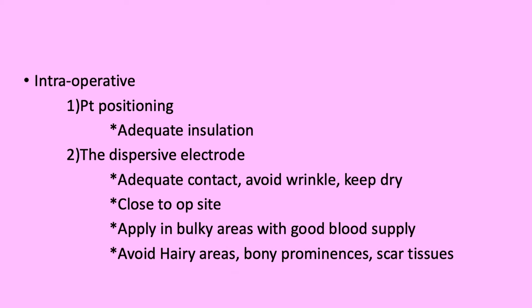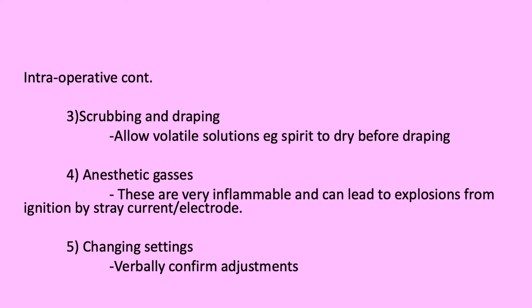The pad should be placed close to the operating site, because the further away it is, the longer the circuit, requiring more voltage to operate, which could result in burns to the patient. We should endeavor to apply the pad in bulky areas with good vascular supply, avoid hairy areas, bony prominences, and scar tissue. Allow volatile solutions like spirits to dry before draping — anesthetic gases are very inflammable and can lead to explosions from stray current or the electrode.